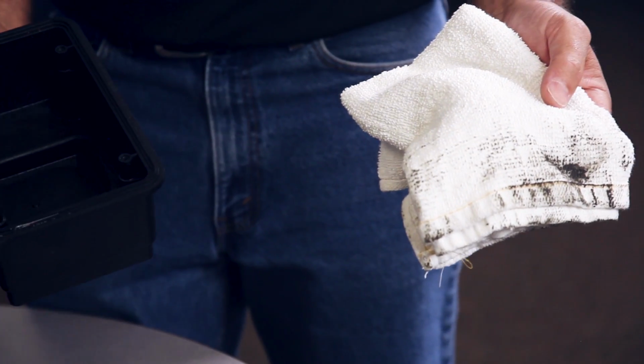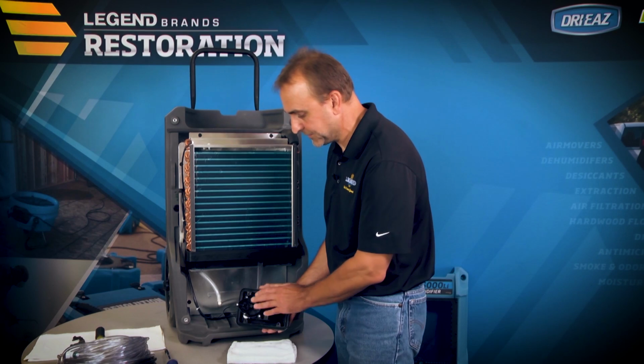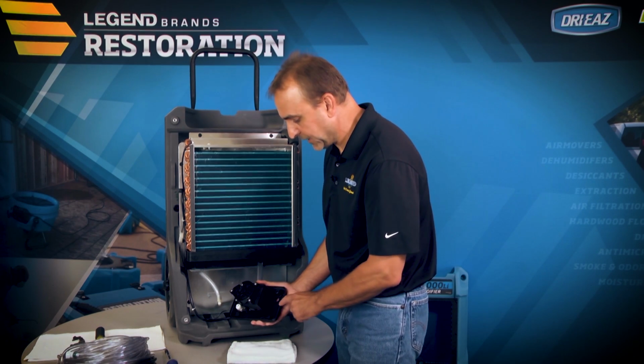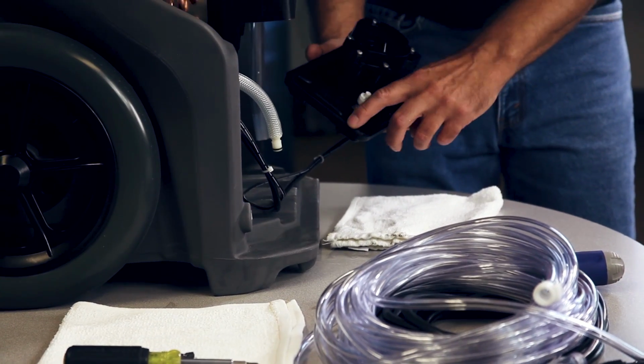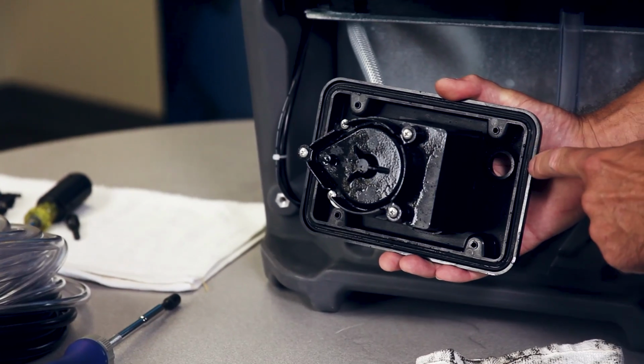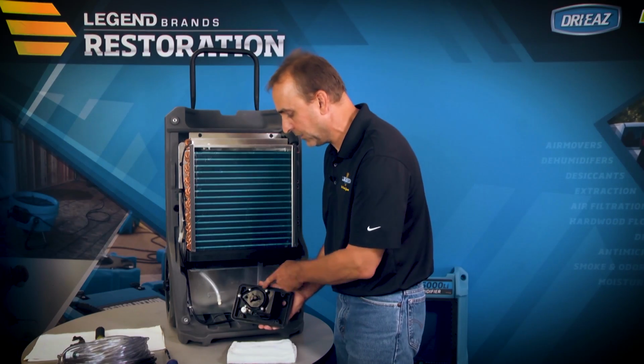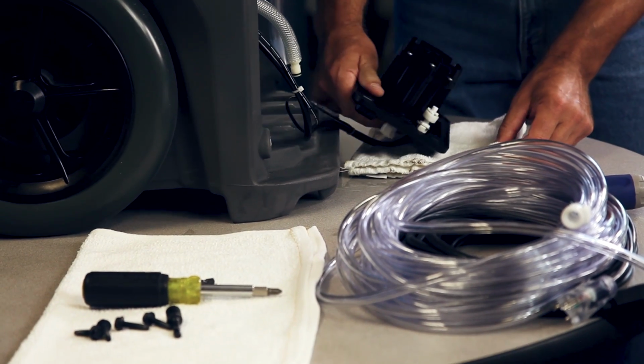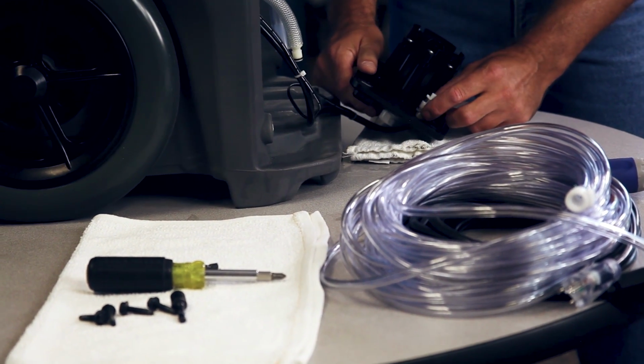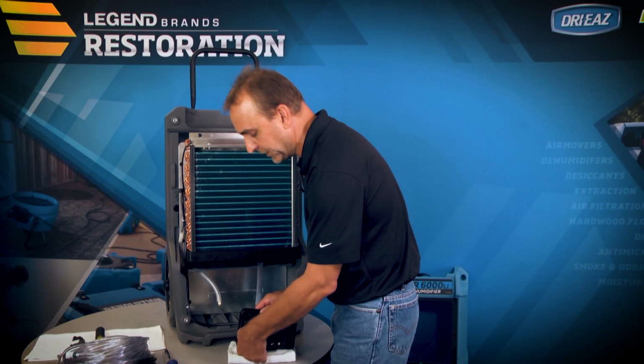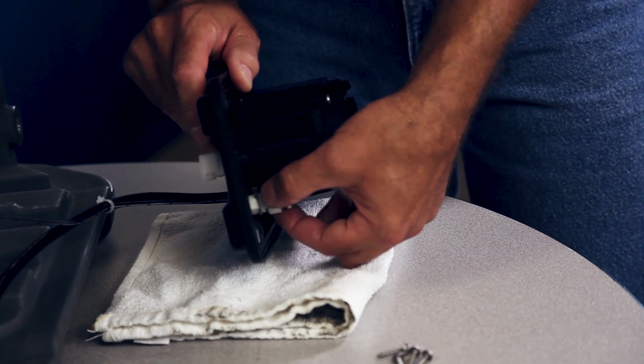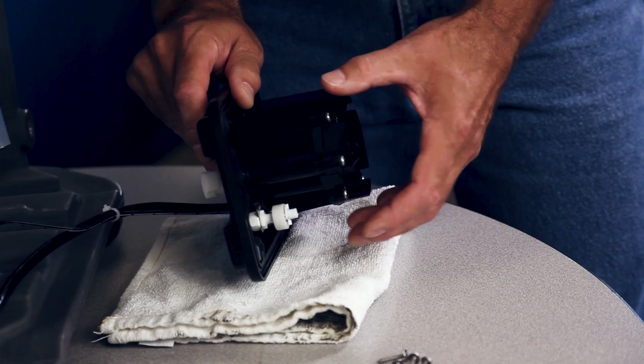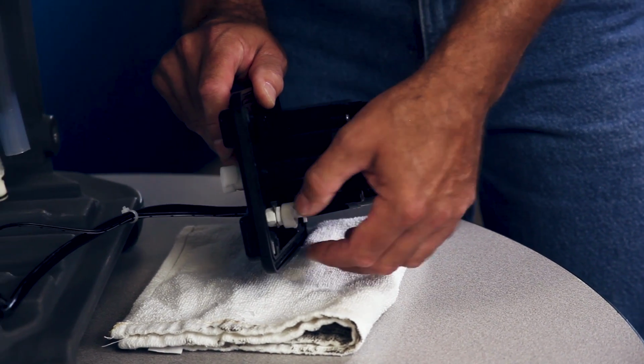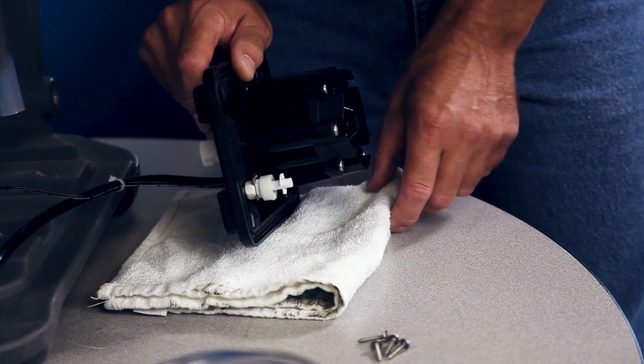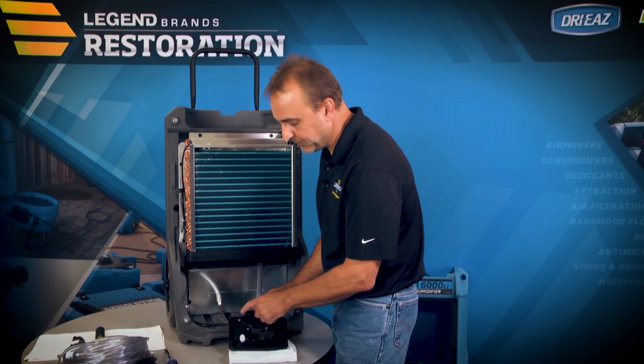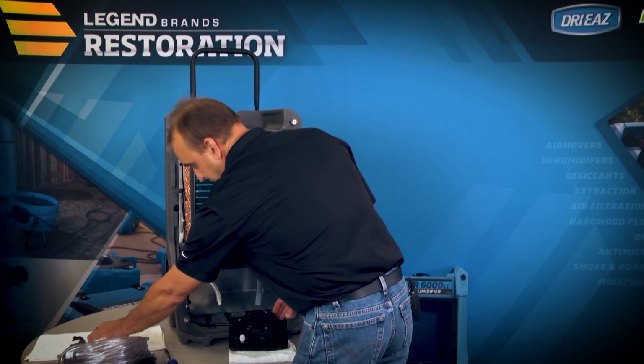After cleaning the condensate sump, you'll want to focus on the condensate pump. Inspect the top cover. Make sure the seal between the sump basin and the top cover is intact and in good quality. Turn the condensate pump housing assembly over. Inspect the safety float switch. The safety float switch engages if there's a blockage in the condensate line and will shut the unit off, generating an ER9 error code. The condensate pump inlet cover should be removed for inspection.